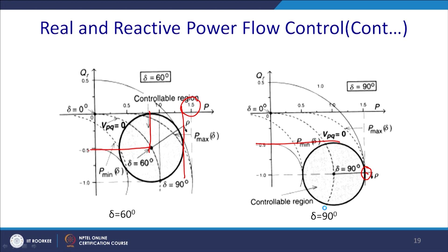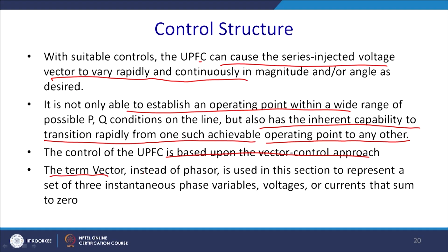So, let us understand this zone of control, and these are the takeaways. With suitable control, the UPFC can cause the series injection voltage vector to vary rapidly and continuously in magnitude and phase angle as desired. It is not only able to establish an operating point within a wide range of possible P and Q conditions on the line, but also has the inherent capability to transition the transmission line rapidly from one such achievable operating point to another. The control of the UPFC is based upon the vector control approach. The term vector, instead of phasor, is used in this section to represent a set of instantaneous phase voltages, phase currents and the sum 0. So, this is the zone of operation and control of the UPFC.